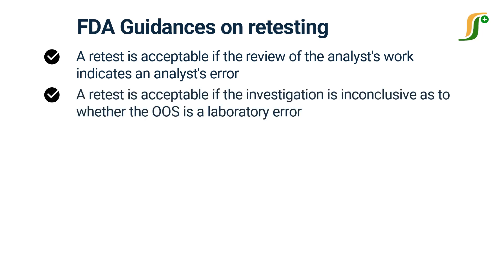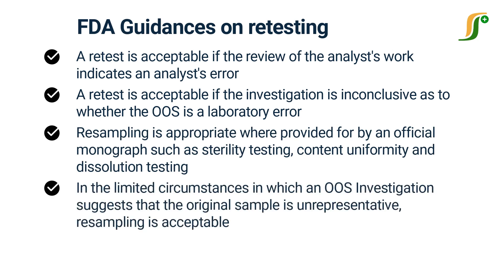Here are some FDA guidances on retesting as a result of out-of-specification investigation. A retest is acceptable if the review of the analyst's work indicates an analyst's error — in this case, limited retesting is required and the original result may be replaced by the retest result. A retest is also acceptable if the investigation is inconclusive as to whether the OOS is a laboratory error and the laboratory needs to determine whether the OOS result is an outlier or a reason to reject the batch. Resampling is appropriate where provided for by an official monograph such as sterility testing, content uniformity, and dissolution testing. In the limited circumstances in which an OOS investigation suggests that the original sample is unrepresentative, resampling is acceptable.